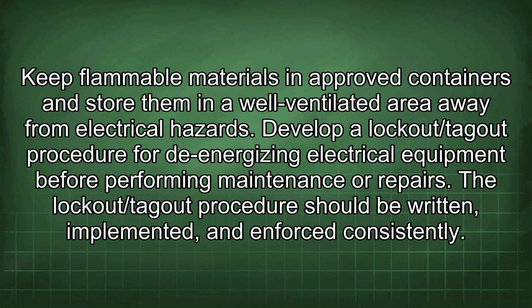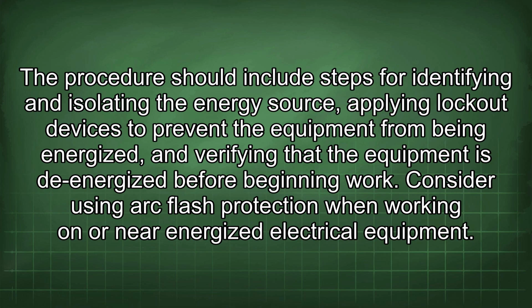Develop a lockout/tagout procedure for de-energizing electrical equipment before performing maintenance or repairs. This procedure should be written, implemented, and enforced consistently. It should include steps for identifying and isolating the energy source, applying lockout devices to prevent equipment from being energized, and verifying that the equipment is de-energized before beginning work.